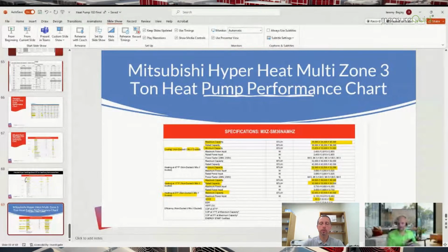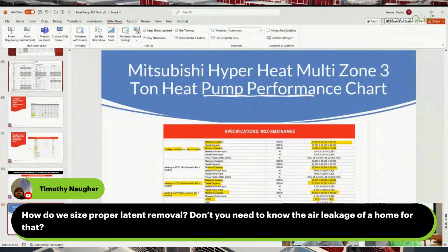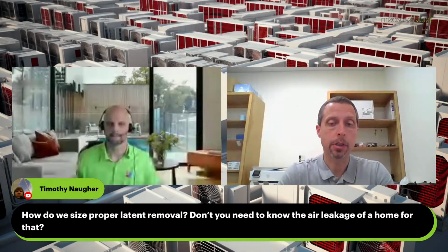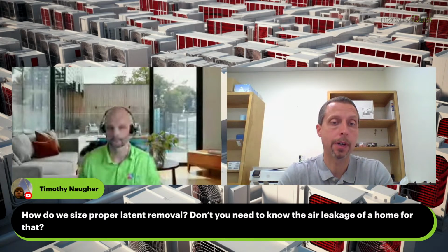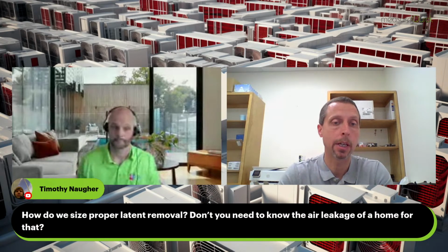Question from Timothy Naugher: how do we size proper latent removal? Especially, don't you need to know the air leakage of that home to be able to size that latent removal properly? I can approach it. That's really going to fall back on your Manual J and how you input information on infiltration and any air leakage into your load calculation. And of course, the most precise way of doing that is if you actually have blower door test data for the home, and you can figure out the amount of leakage, assuming it's uncontrolled leakage. We're not bringing this in as ventilation air, let's say.